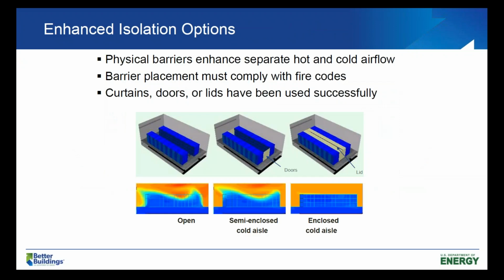And then there's a whole range of barriers that can be put in a hot aisle or cold aisle to force the air to go where you want it to and not where you don't. And there's some simulations at the bottom, and these can be done again in the hot or cold aisle. One thing to remember is that putting barriers in a data center may block access to fire and smoke detection and suppression systems, and so any changes need to be done in coordination with your fire authority. But they can be very effective. Next slide, please.